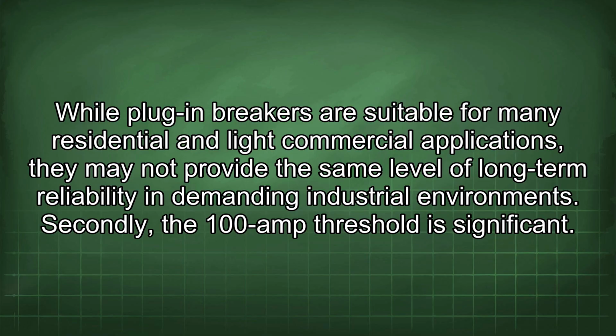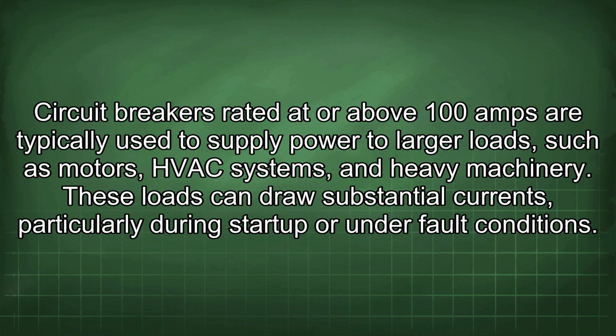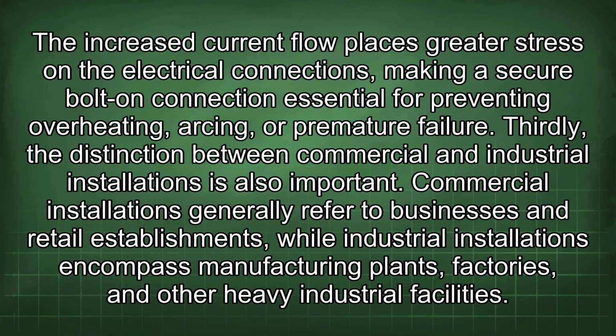Secondly, the 100 amp threshold is significant. Circuit breakers rated at or above 100 amps are typically used to supply power to larger loads such as motors, HVAC systems, and heavy machinery. These loads can draw substantial currents, particularly during startup or under fault conditions. The increased current flow places greater stress on the electrical connections, making a secure bolt-on connection essential for preventing overheating, arcing, or premature failure.